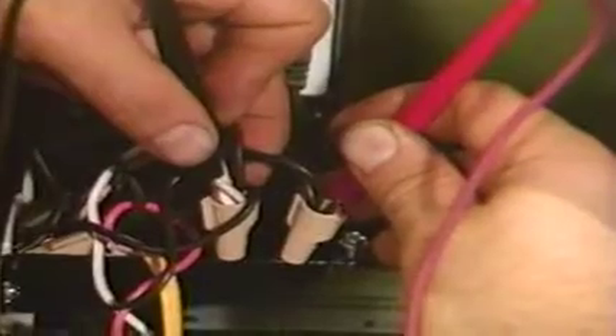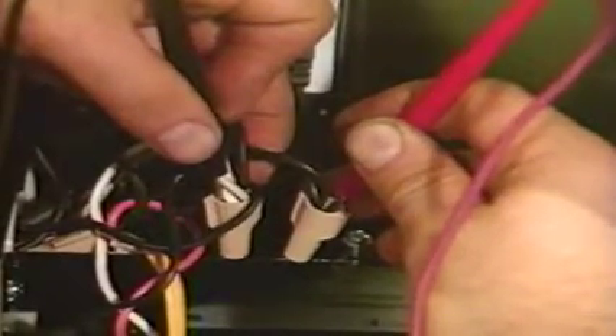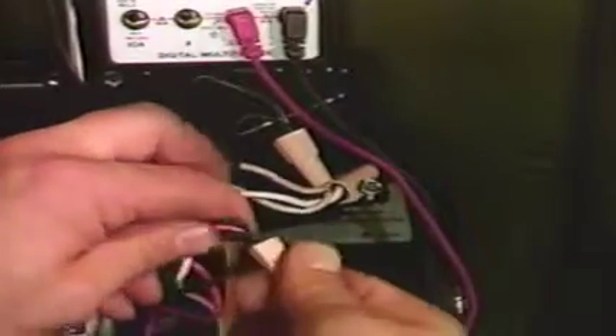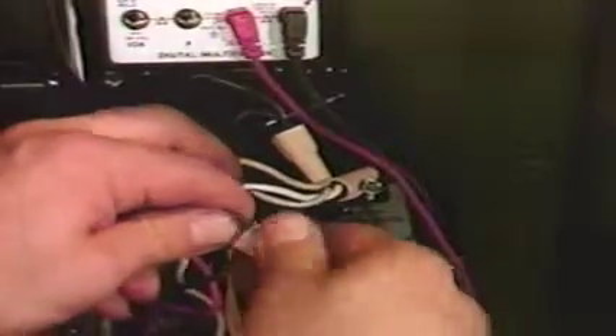What if the relay didn't pull in at all? If that were the case, start by measuring the electric input for 115 volts between the primary L1 hot and the L2 neutral leads. Jumper in the thermostat TT terminals to make sure power is reaching the primary control. Check the connections for looseness. What if the relay does pull in? Check to see if the CAD cell is seeing enough light.